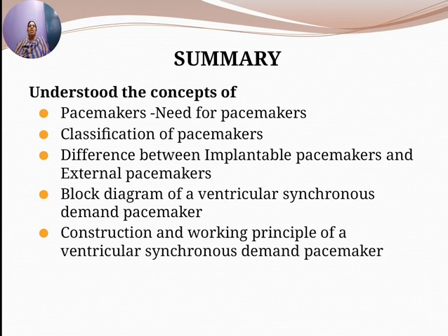The ventricular inhibited pacemaker and demand synchronous pacemaker are almost the same. Only, either type of the ventricular programmed pacemaker is able to sense the presence or absence of an R wave. In the case of demand pacemaker, the output of the pacemaker is suppressed as long as the R wave is present. Thus, its output is held back or inhibited when the heart is able to pace itself. But in case of synchronized pacemaker, it is triggered rather than inhibited by the R wave.